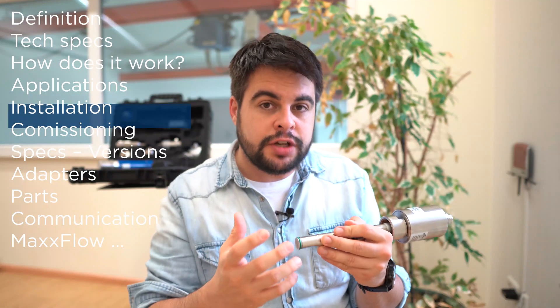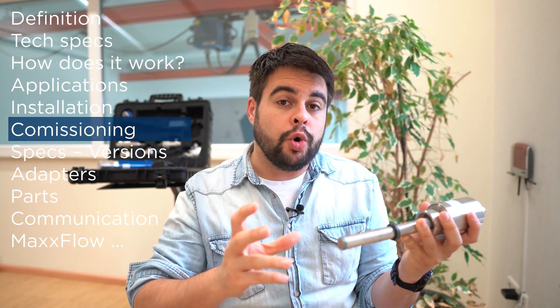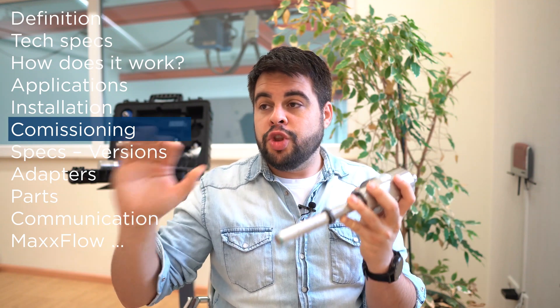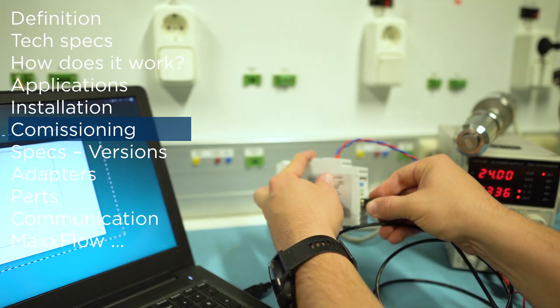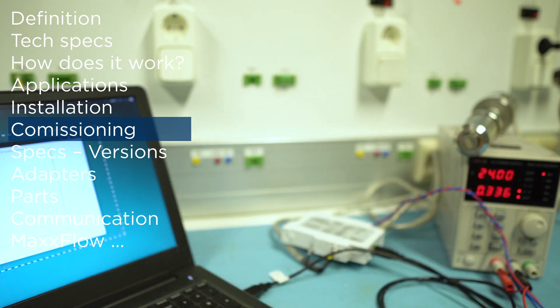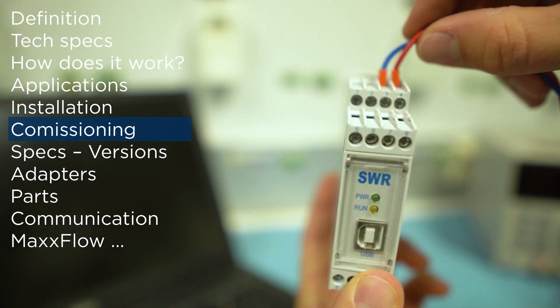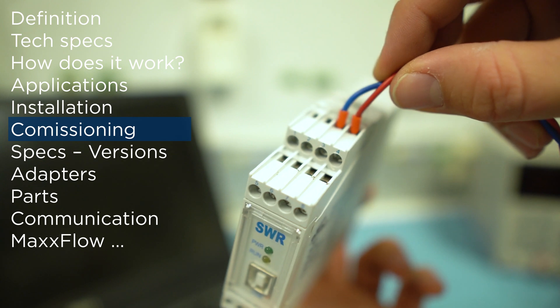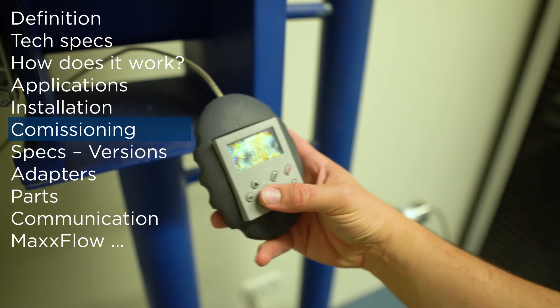And how do you commission MaxxFlow? First of all, we have to consider the situation without flow. With no material, we insert the sensor and using the software or the evaluation unit, we set the zero point to identify noise, for example. With the zero point, we get the lowest signal.